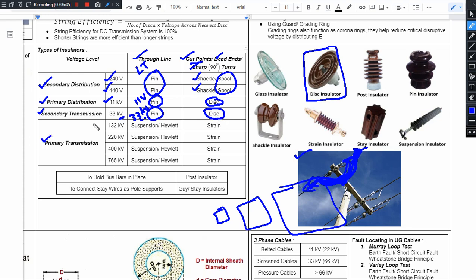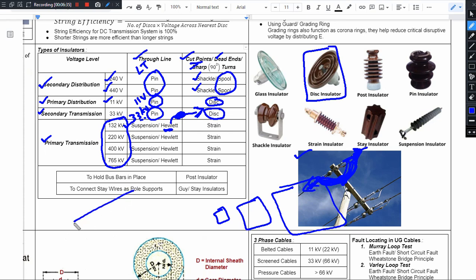For primary transmission (132 kV to 765 kV), on the through-line we use suspension insulators. A suspension insulator is a heavy insulator — a string of discs is suspended from a tower point. At turnings and dead-ends in primary transmission, strain insulators are used.